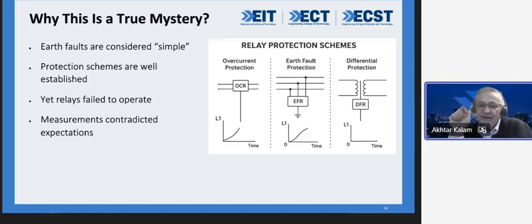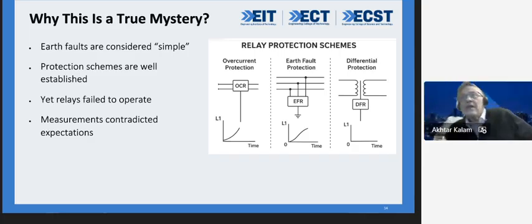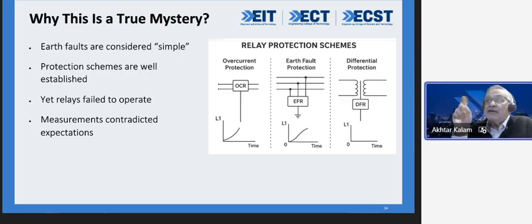And that overconfidence of an engineer is dangerous. It's not the system, it is not anything of that sort, but that overconfidence that we can solve this issue is dangerous. And I'll show you. So, you might have the best protection scheme in the world, and the system failed. It failed because it failed to operate. It gave contradictory measurements. All these were purely because now we are talking about the modern power systems.